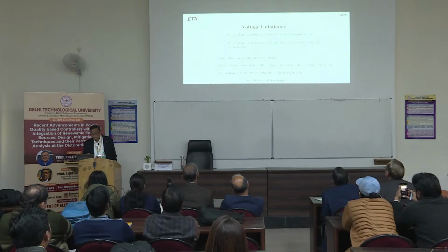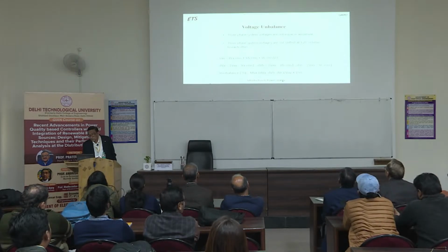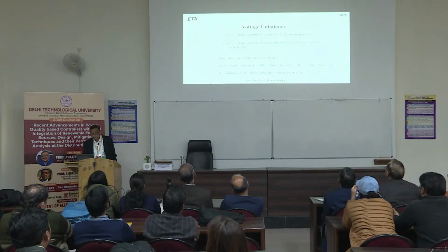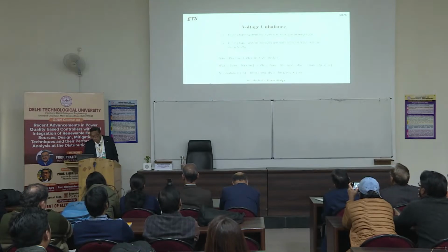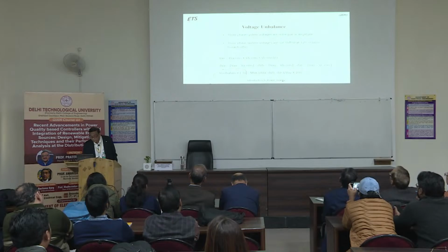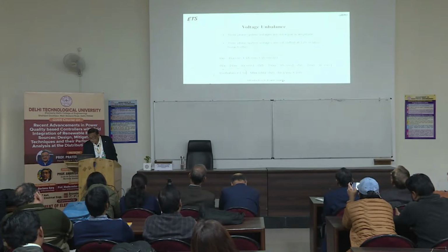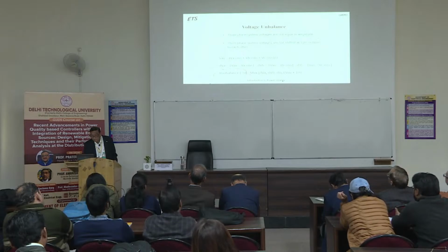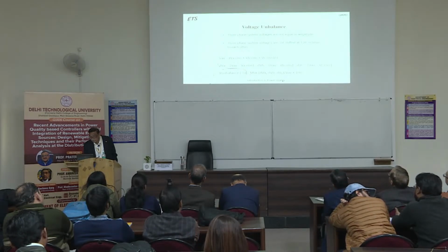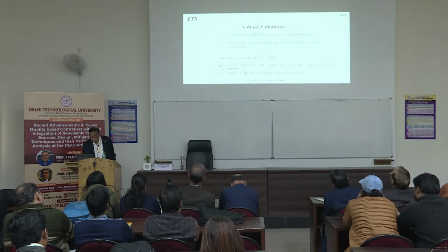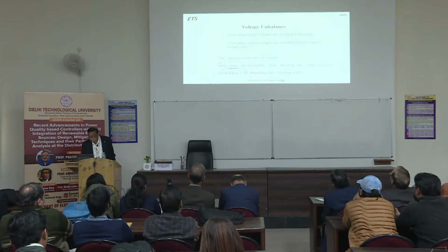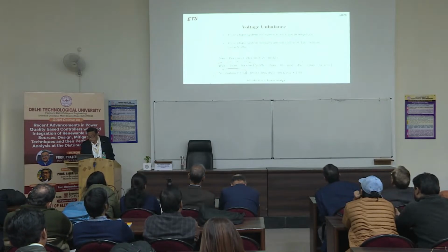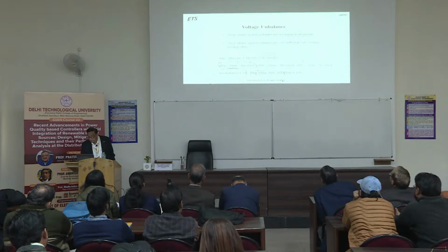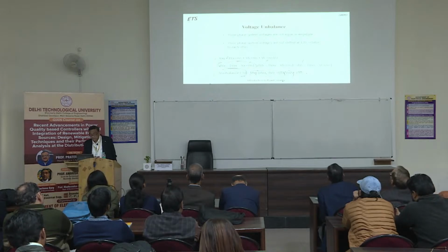Voltage unbalance. Three-phase system voltages are not equal in amplitude, or they are not shifted at 120 degrees relative to each other. So how do you calculate the voltage unbalance in percentage? This is the maximum deviation: the deviation in phase A voltage, the difference between the average voltage and VRMS, or phase B, DVB, or phase C. You see which one is maximum, divide by the average voltage and multiply by 100, and it will give you the voltage unbalance in percentage.